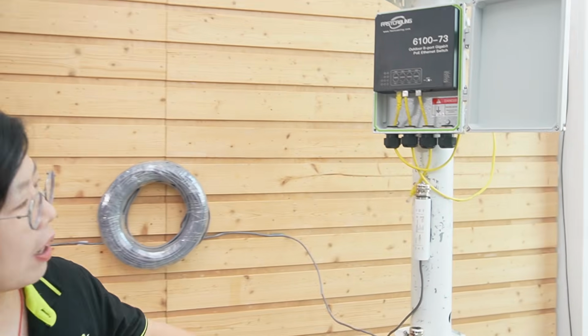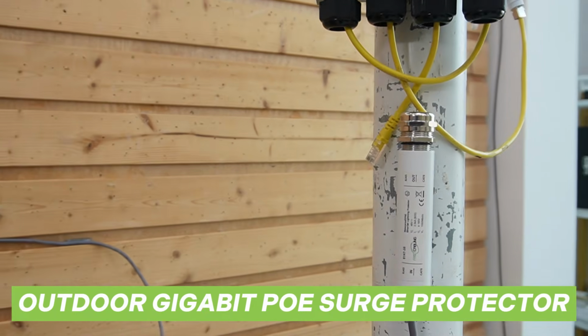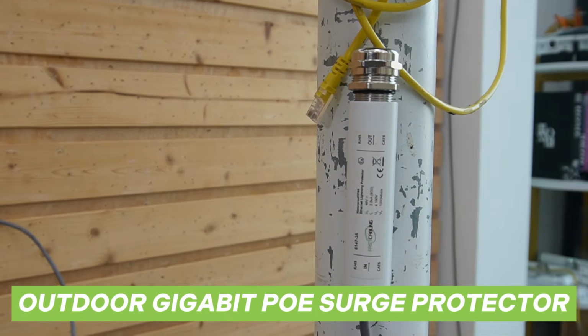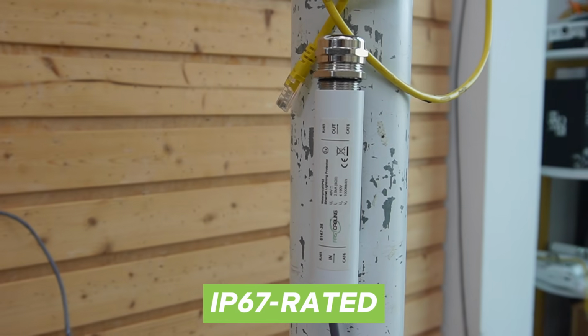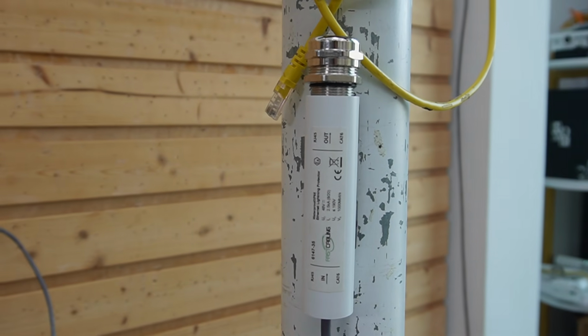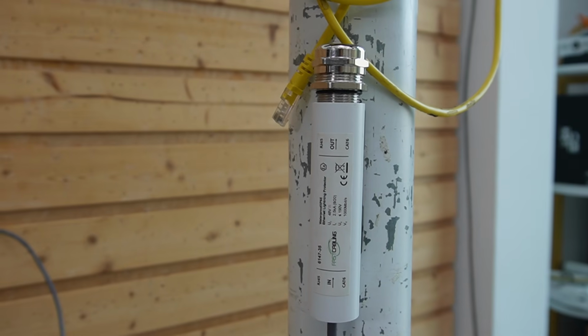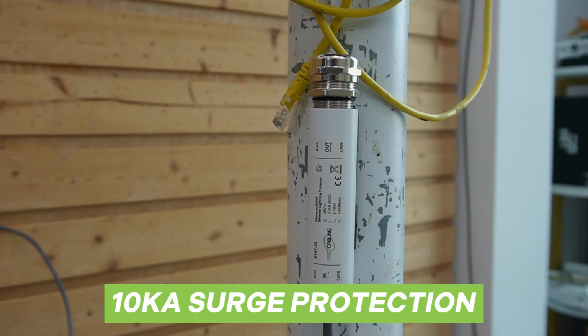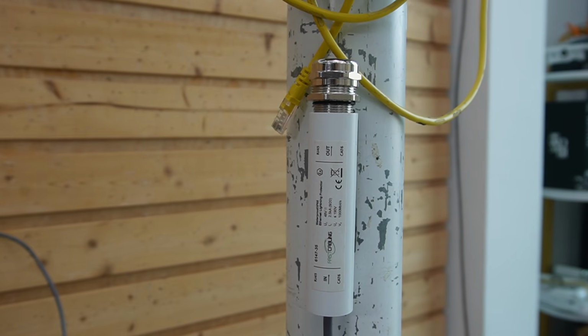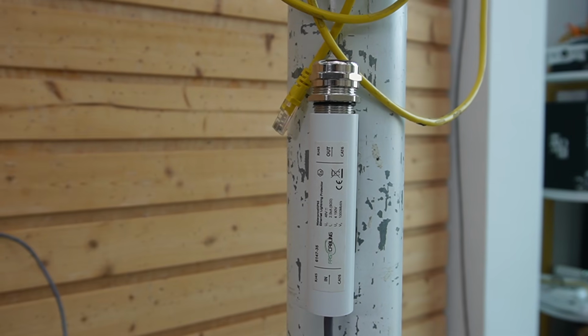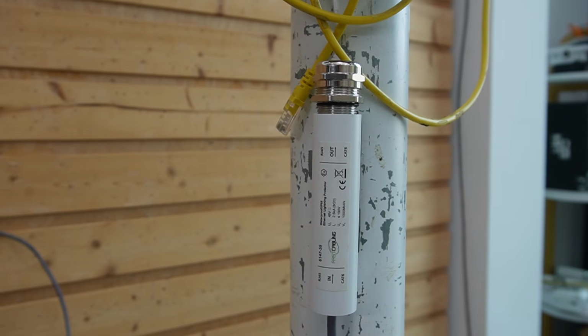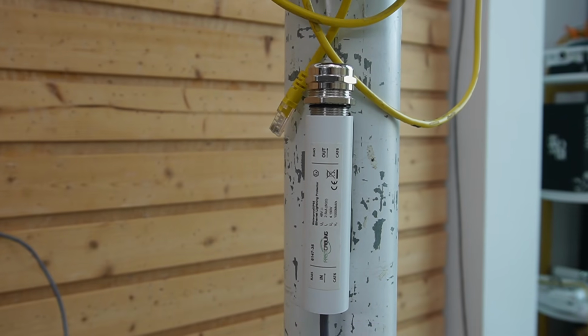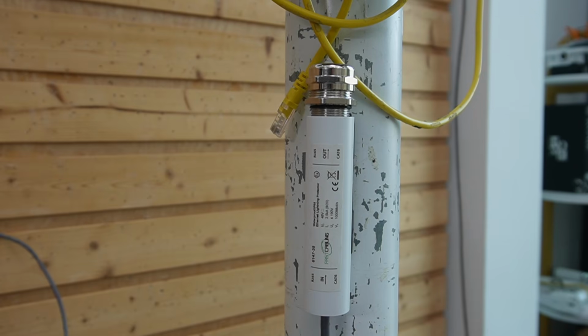So for the outdoor run, we're using this outdoor gigabit PoE surge protector. This is a rugged IP67 rated device that mounts right next to our pass-through switch. It provides 10 kA surge protection against lightning-induced spikes and static. It supports gigabit speed and is fully compatible with IEEE 802.3 AF, AT, and BT standards.